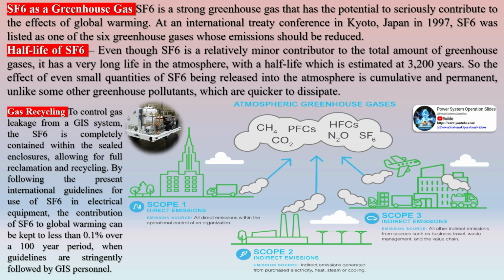Even though SF6 is a relatively minor contributor to the total amount of greenhouse gases, it has a very long life in the atmosphere, with a half-life which is estimated at 3,200 years. So the effect of even small quantities of SF6 being released into the atmosphere is cumulative and permanent, unlike some other greenhouse pollutants, which are quicker to dissipate. Gas recycling. To control gas leakage from a GIS system, the SF6 is completely contained within the sealed enclosures, allowing for full reclamation and recycling.